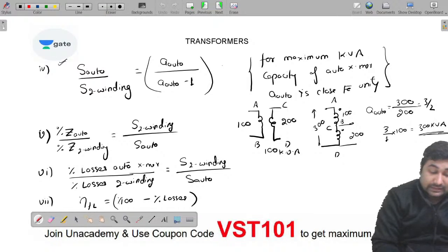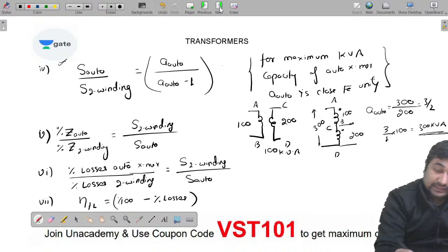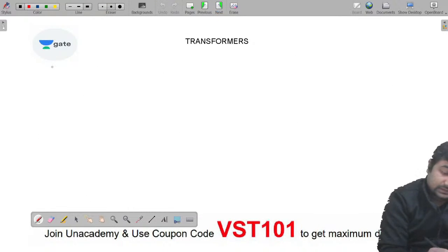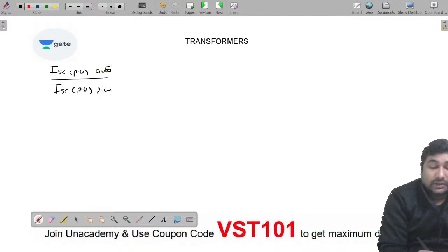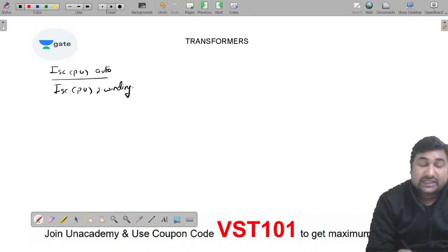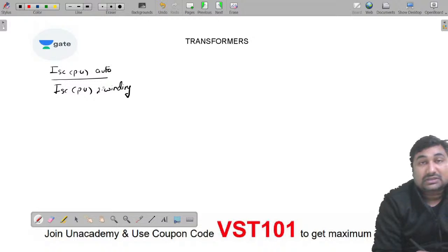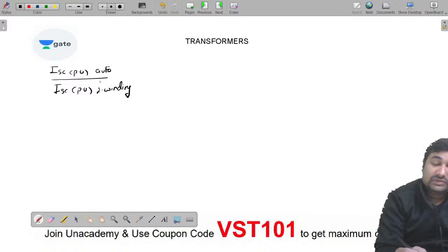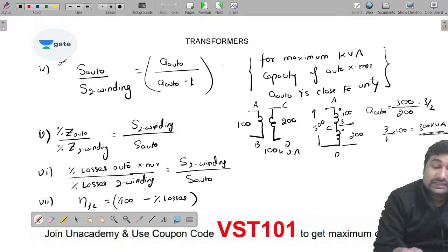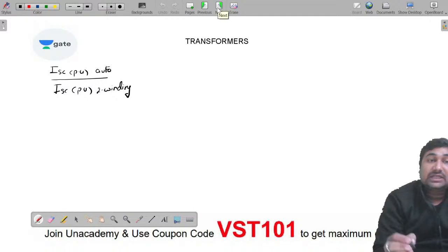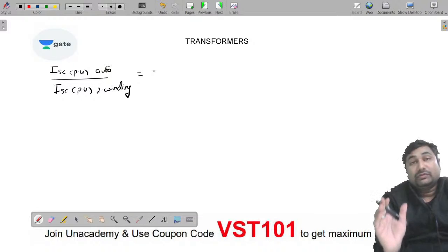Now please see, come to the next part, that is your short circuit current. So per unit short circuit current in case of auto transformer to per unit short circuit current in case of two winding transformer. Always remember that the greatest disadvantage of connecting a two winding transformer as an auto transformer is the short circuit current, and this current increases because of the decrement in the percentage impedance. Is it okay? So that is why we never connect a two winding transformer as an auto transformer. Whenever we have to design an auto transformer, we always try to go with a fresh one.